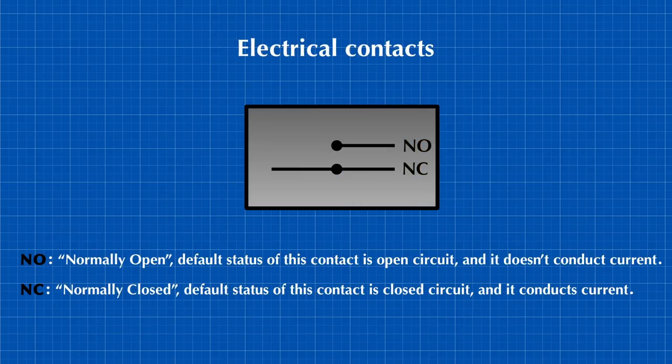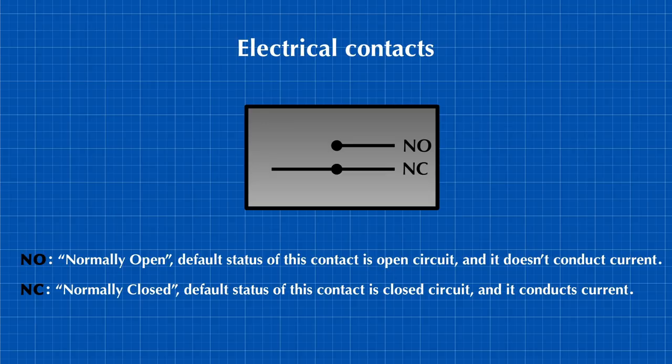Buttons and switches have normally open and normally closed contacts to suit different types of functionality, but emergency push buttons and switches must be connected using the normally closed contact, not the normally open one.